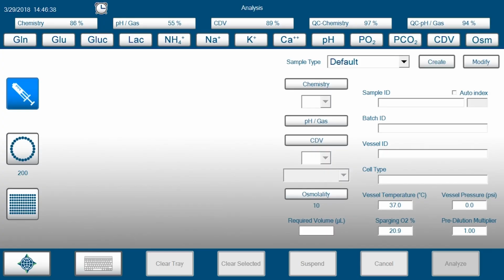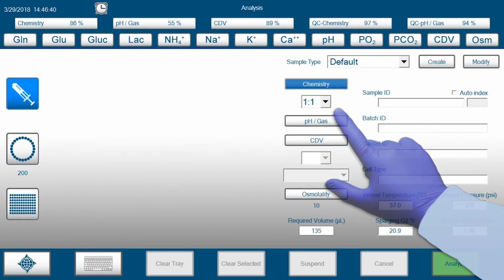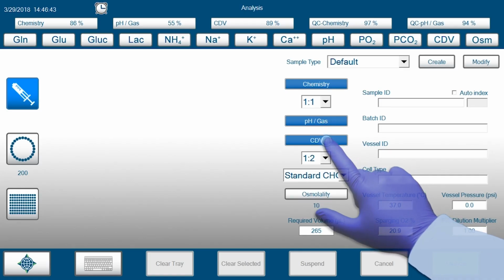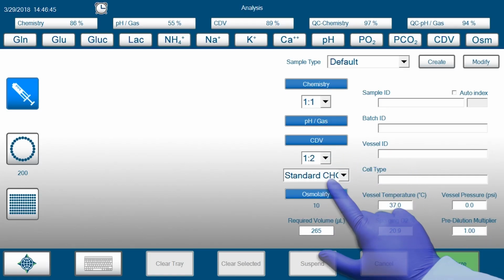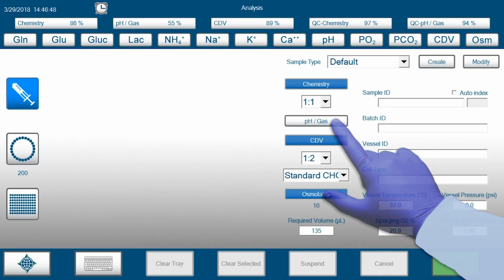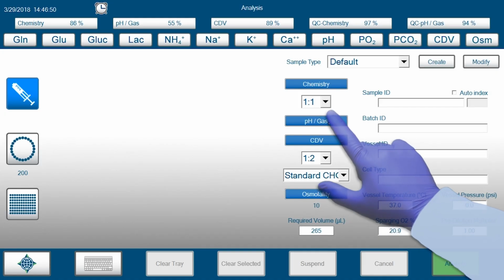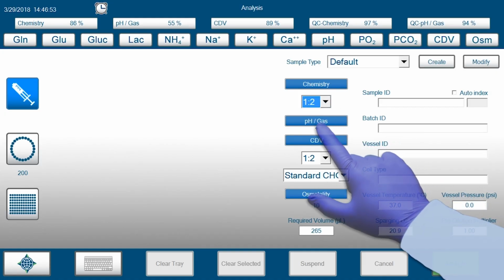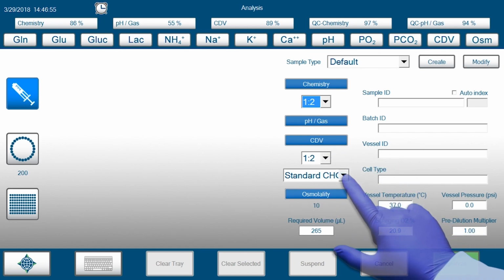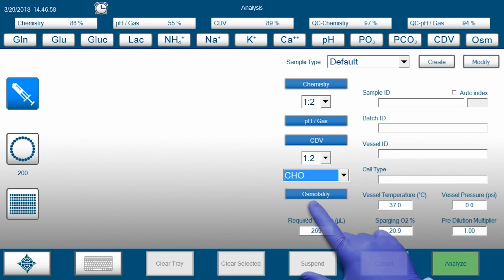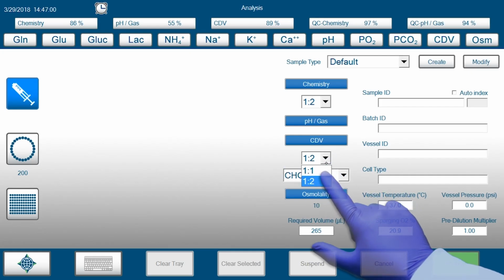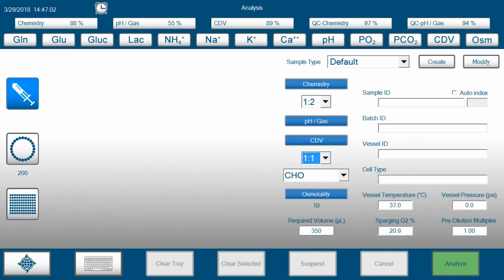You can select and deselect which modules you would like included in the analysis by tapping on the module. The selected modules appear in blue. For the chemistry and CDV module, you can also select an onboard dilution. It is important to select the appropriate cell inspection type when running the CDV module to ensure accurate cell counts. You will notice, as you are selecting modules, that the required volume is displayed at the bottom of the screen. The maximum volume the system will aspirate in manual mode is 350 microliters.